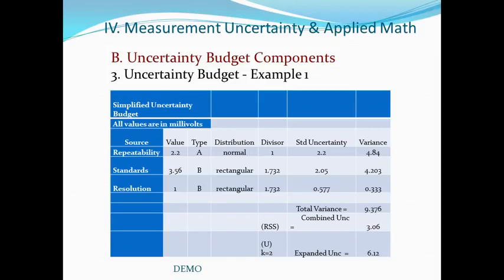And then we can calculate from that the combined uncertainty, which is the same as doing the RSS value of the standard uncertainty column. So taking the square root of the variance, 9.376, we end up with an RSS value, or a combined uncertainty for the three items of 3.06 millivolts.